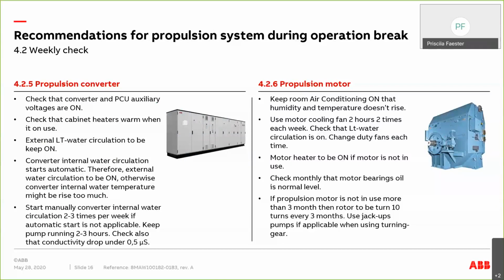Typically, propulsion converters are water cooled, and then the water circulation should be used regularly. Normally it starts automatically, but if not, then it has to be started manually. Again, on a weekly basis, 2-3 times per week, just to have water rotating inside the pipelines. If that is not done, the water starts to get all kinds of bacteria and start to grow some weeds and all kinds of stuff, which is then difficult to remove afterwards.